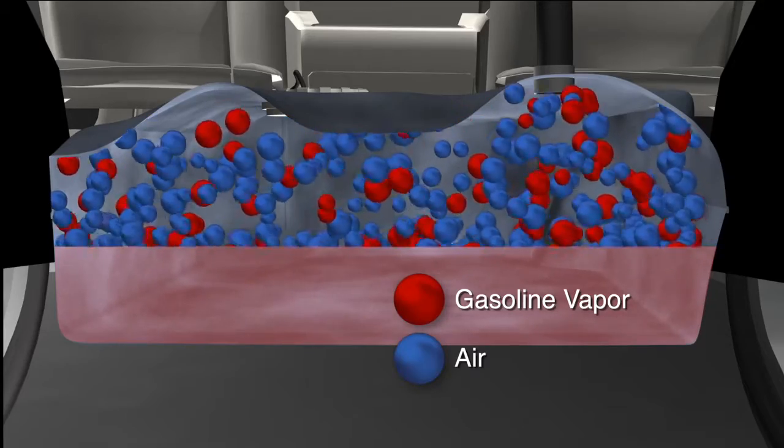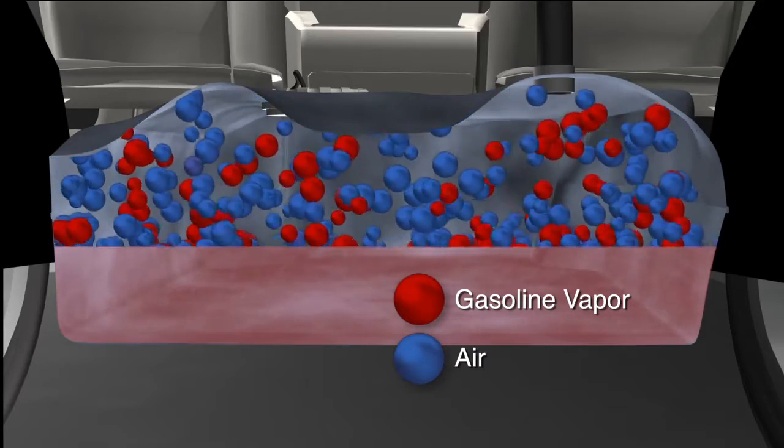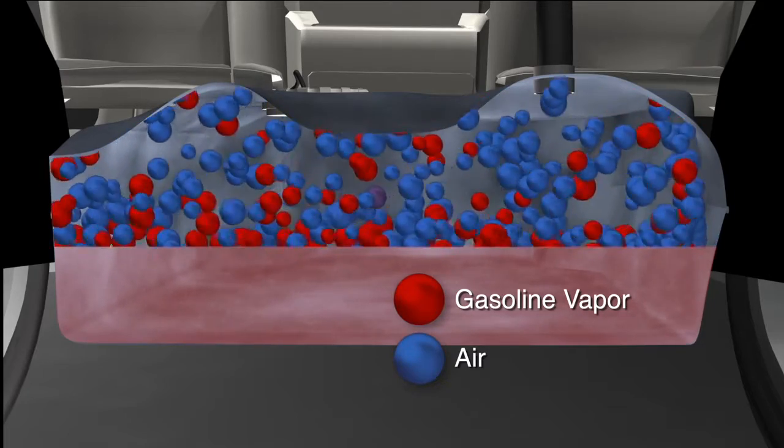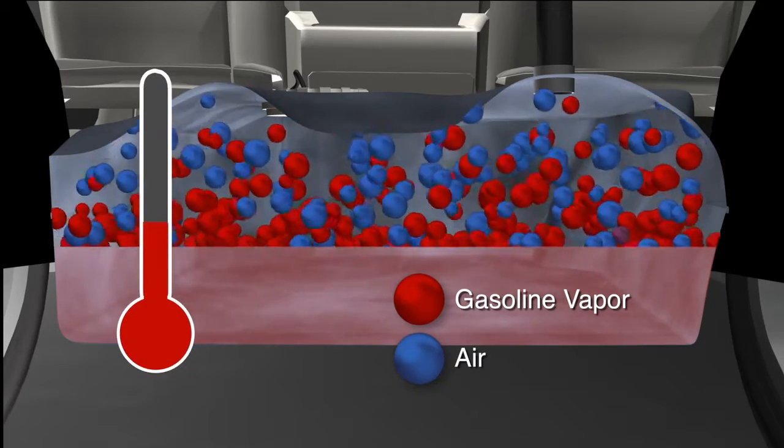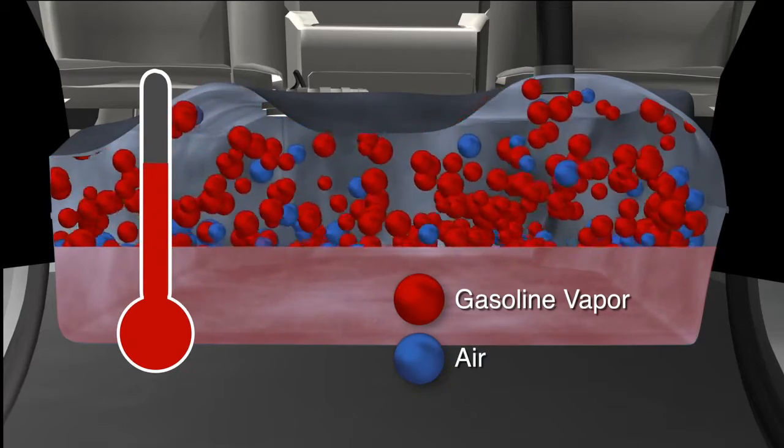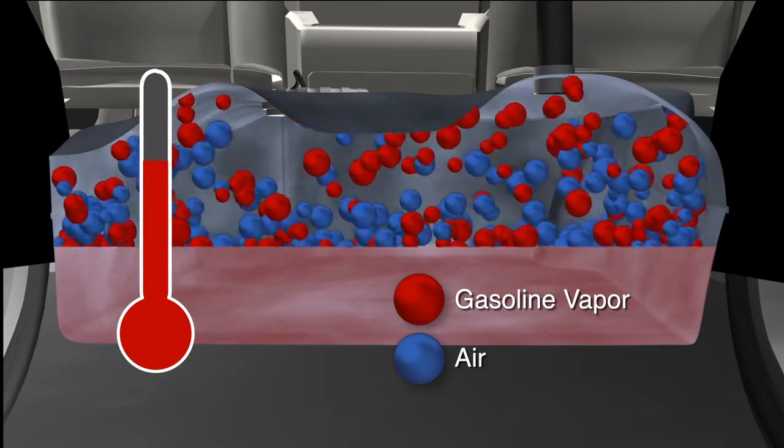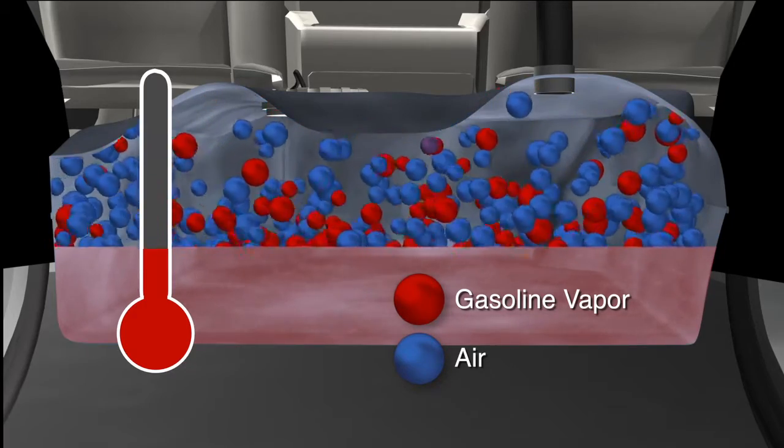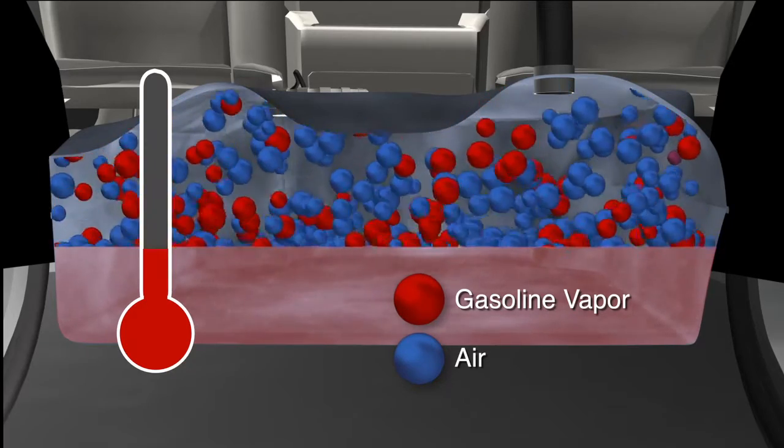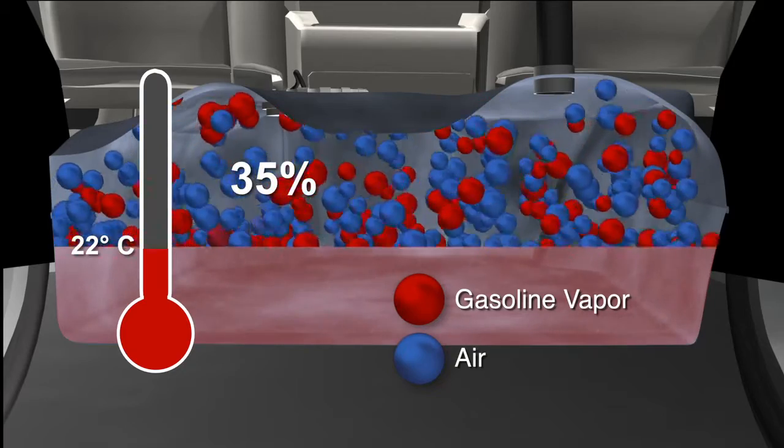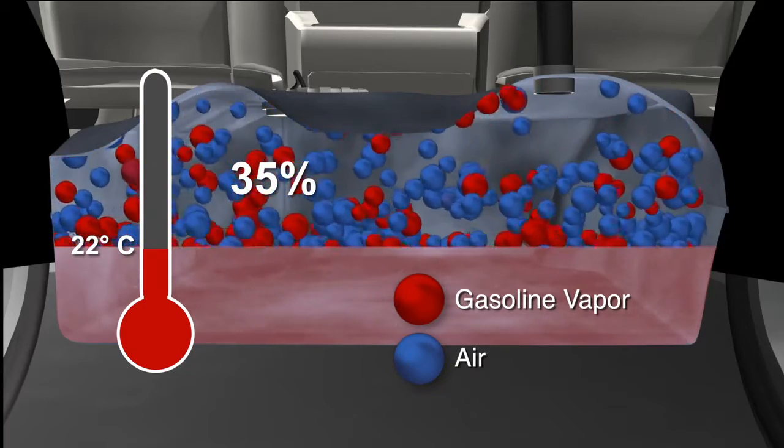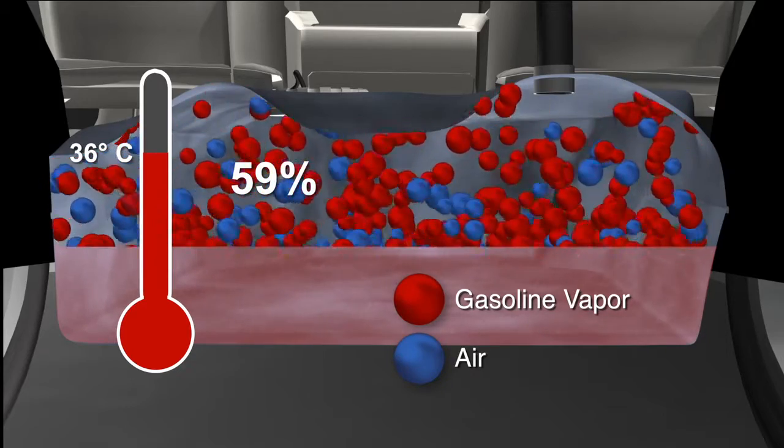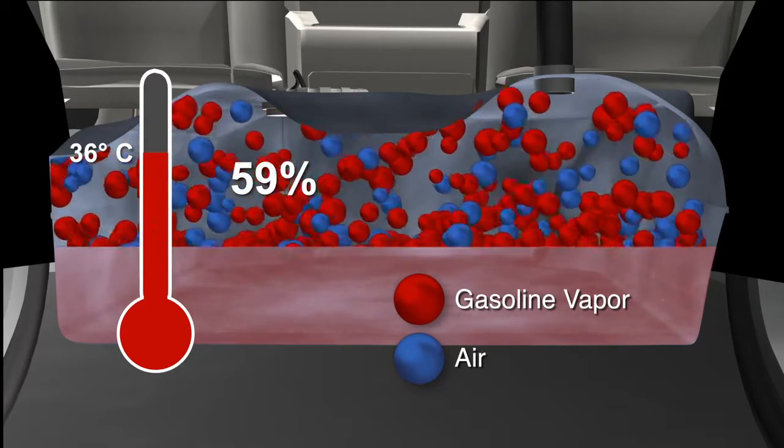Gasoline is a volatile substance. Volatility is a measure of the tendency of a substance to vaporize. As temperature increases, vaporization increases and alternately, a decrease in temperature reverses the process. That's why a storage tank filled with gasoline can have a gasoline vapor concentration of 35% at 22 degrees Celsius and 59% at 36 degrees. And there are other factors that can affect volatility.